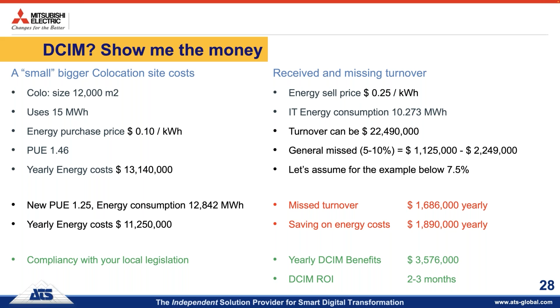The other part is the missed turnover due to faulty invoicing. So if you're selling your energy at 25 cents per kilowatt hour, and based on these numbers again, 15 megawatts, PUE 1.46, you have an energy consumption on IT of 10 megawatts. So your turnover will be $22.5 million. But in general, if you miss 5 to 10%, you are missing something between 1 and 2.2 million yearly. So let's assume it's just in the middle. In that case, we miss almost $1.7 million. So just doing those two steps, improving efficiency and making sure that your invoicing is right, brings you $3.5 million yearly, which brings the ROI of a DCIM solution to just 2 or 3 months.